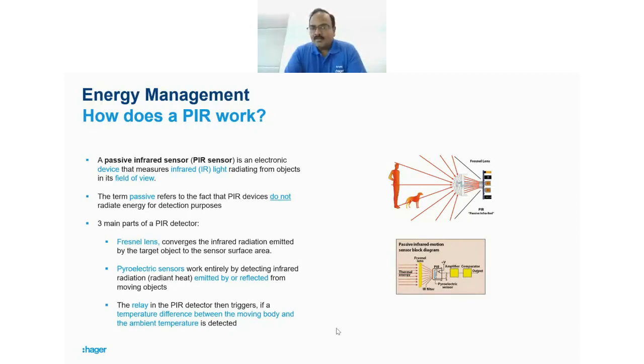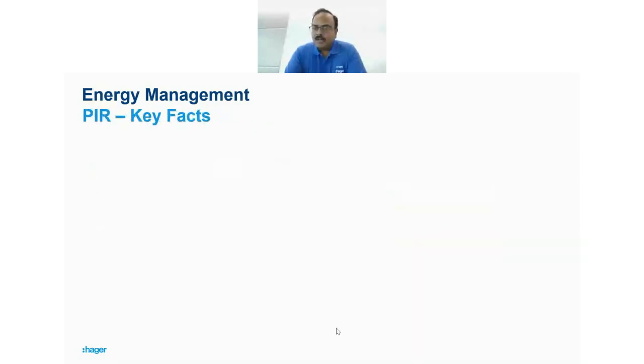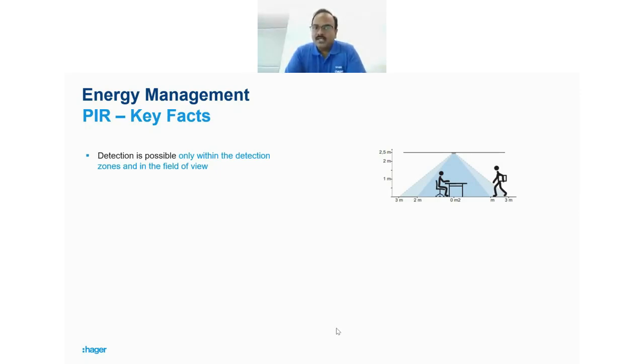Some key facts about PIR use: first, it can only detect within the detection zones specified in the technical sheet. For example, a product with a 6-meter diameter detection zone — 3-meter radius — means that if a room is 8 meters wide you may need two units. This is the first understanding. Second, it requires a clear field of view — if a shelf is blocking the path, it cannot sense movement in that area.